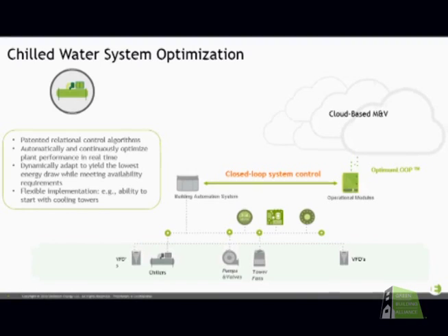So setting up the system architecture that is traditional, that you mostly see for current plants. We talked a minute ago about all these items on the bottom, VFDs, everything that sits within the chill water plant, chillers, pumps, cooling towers, that feeds up into what we call a sensor level. So we have meters. This can be power meters, BTU meters, so you're able to measure both those two key markers, the input in terms of energy and the output in terms of cooling. And it's controlled by the building automation system. So that piece is pretty typical on most larger plants that are being constructed today.